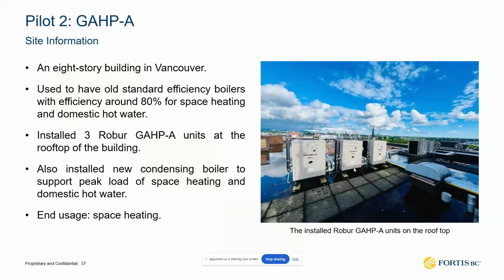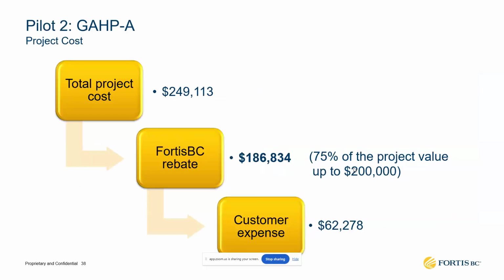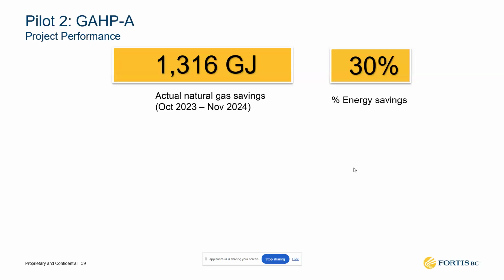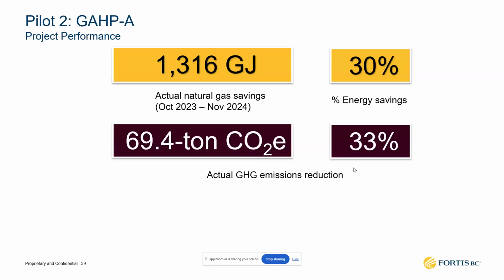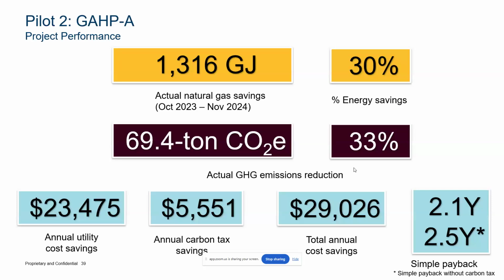Again, around $250,000, and this is a little bit old, but just to give you an example, we provided 75% of the project value. The customer put in the remaining 25%. There were 30% savings compared with the pre-retrofit condition, and around 70 tons of CO2 reduced. And again, the economics are a little bit messed up because of the carbon tax, but these are the results: 2.1 to 2.5 simple payback with and without the carbon tax.